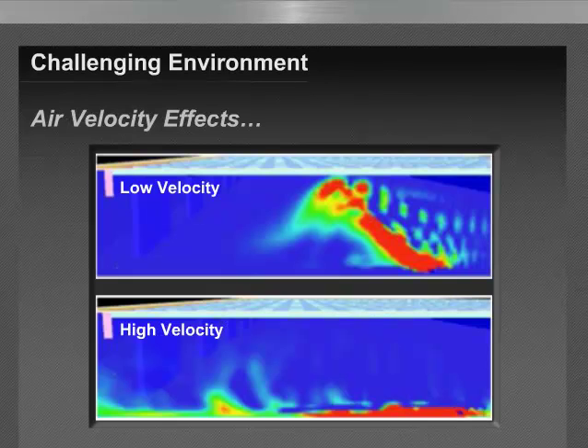We then look at air velocities. Airflow interferes with the normal dispersion of smoke, as can be seen in this particular illustration, two illustrations. If you compare the two illustrations, it's quite apparent to see the behavior of smoke under a low velocity condition and its performance under a high velocity condition. So the resulting effect is reduced predictability of conventional detector performance in high air velocity environments.